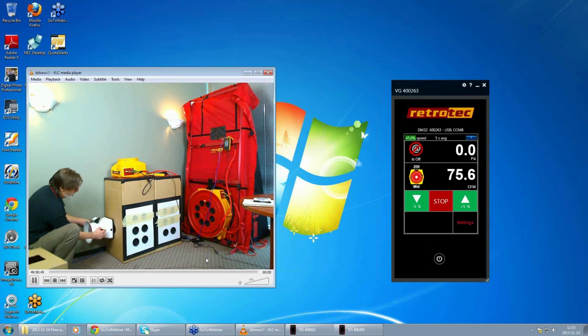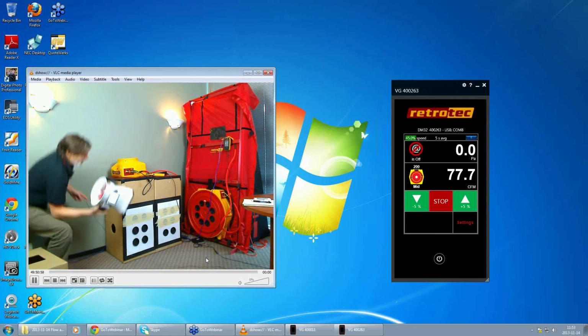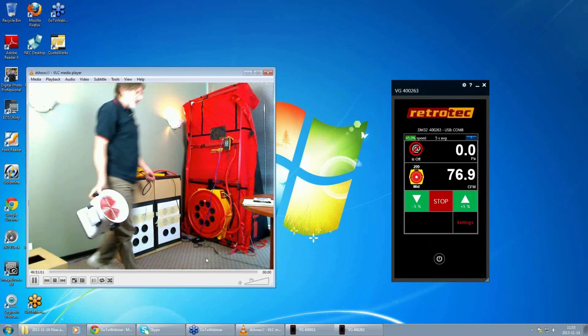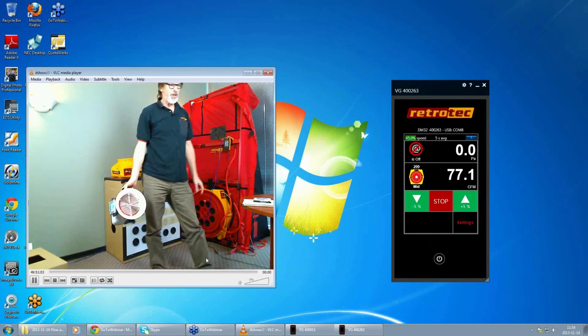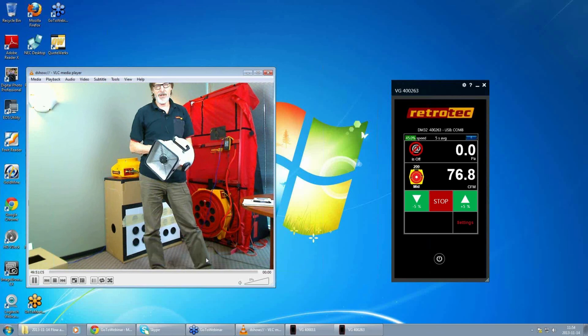So I noticed in doing a house the other day with this that there was a big return, and I actually measured the return in 4 separate pieces, and I got a result that was pretty close. There's nothing out there that will do this. The reason why it can is that it has a pressure zeroing sensor in here that's accurate to a hundredth of a Pascal.